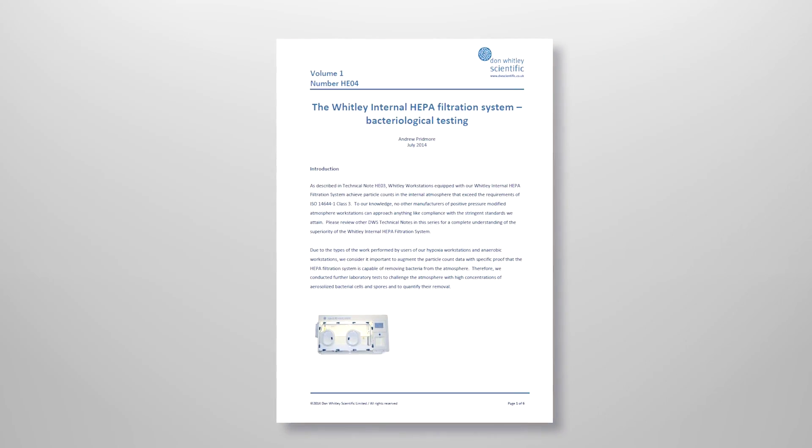These results correlate with the particle count data and demonstrate that the required level of atmospheric cleanliness is regained well within the 20 minutes set out in the standard. If you wish to read more about these tests, a copy of the technical note HE04 is available on our website.